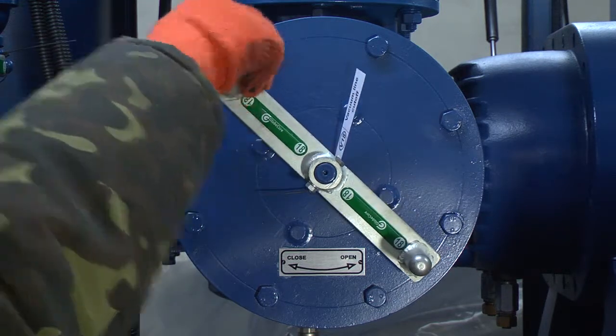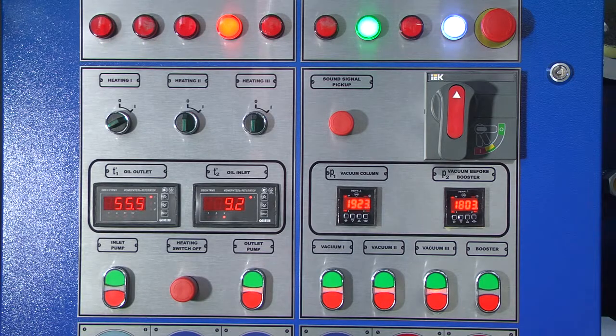When pressure in the column reaches 3000 pascal and no foaming is present, start the pump VP4 and vacuumize the column until the end of intensive gas emission and pressure of 100 PA or less.